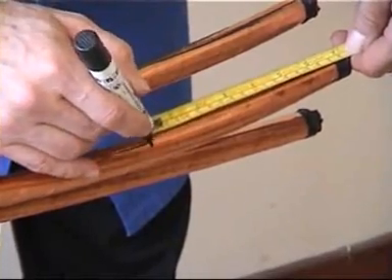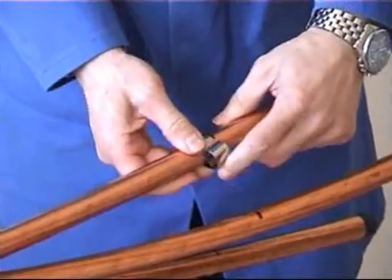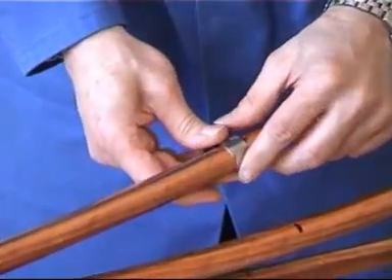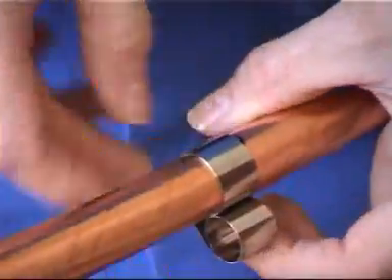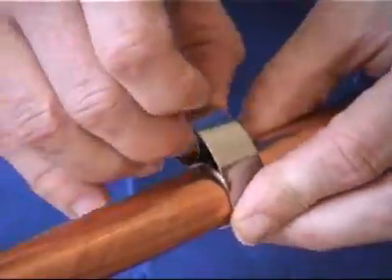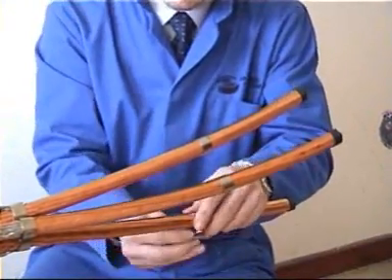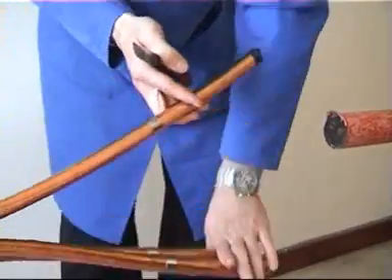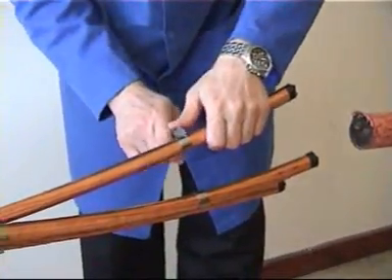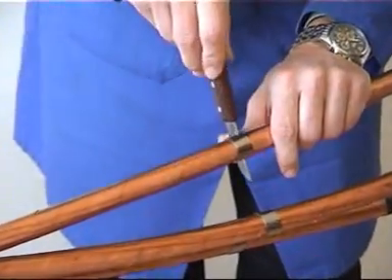First off, make your measurements according to the installation instructions. If copper tape screens are present, we use a roll spring to gain a straight edge. Then with a sharp knife, you can score around the edge of the roll spring.